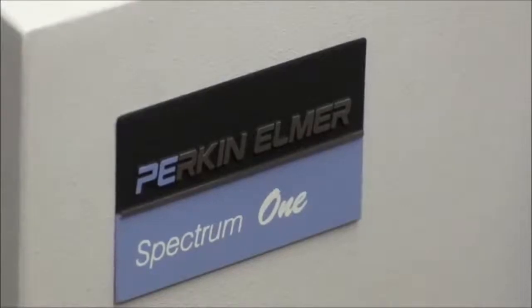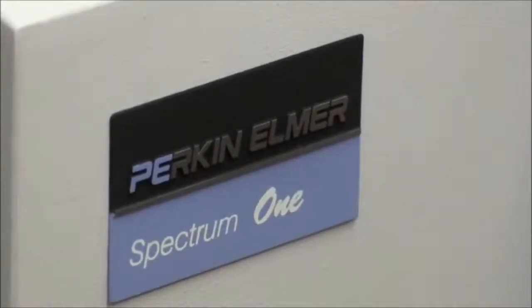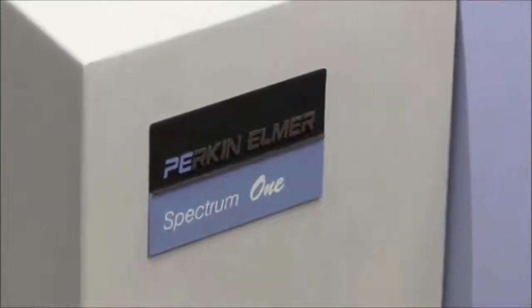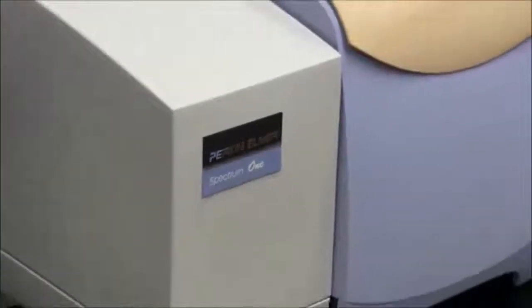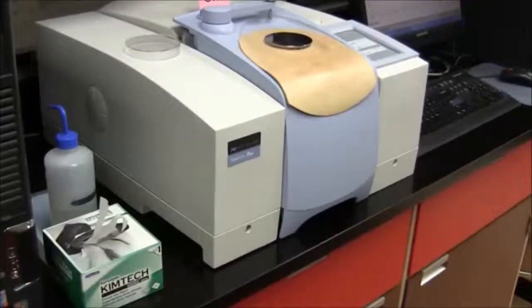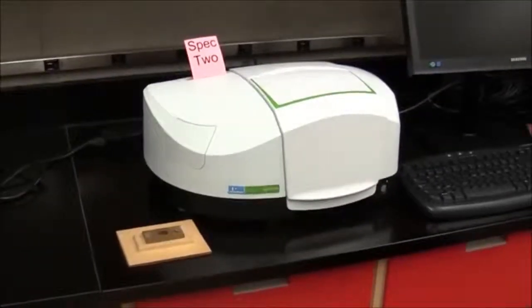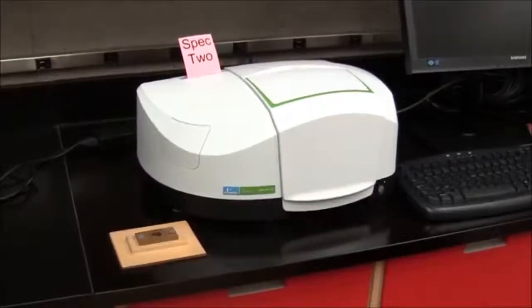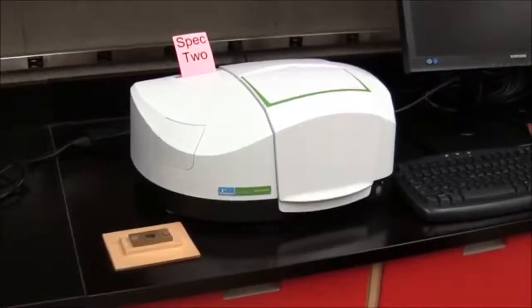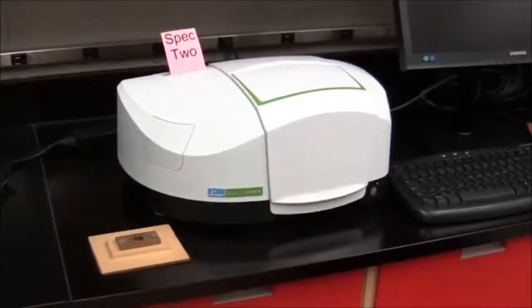The chemistry department owns two Fourier transform IR spectrometers, often just called FTIR. The first is a Perkin-Elmer Spectrum 1 FTIR, which we refer to as Spec 1. And the other is a Perkin-Elmer Spectrum 2 FTIR, which we refer to as Spec 2.